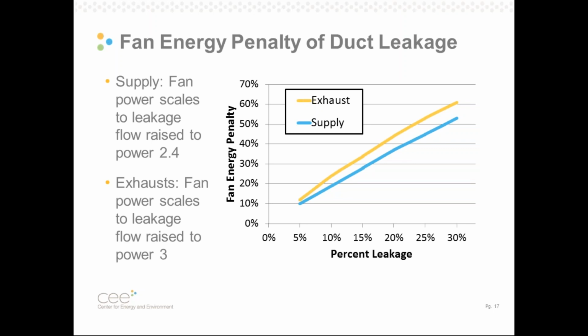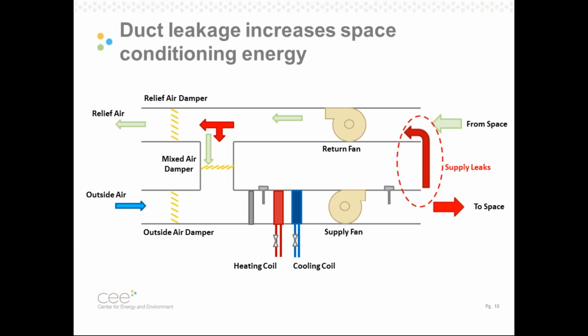I mean, these are major, major inefficiencies. If you can imagine in a building with a lot of air handlers, if you aggregate duct leakage over a lot of these big blowers, we're talking about tens, if not hundreds of kilowatts of wasted fan energy. It doesn't really end there. In some systems, we have significant thermal penalties also associated with duct leakage.